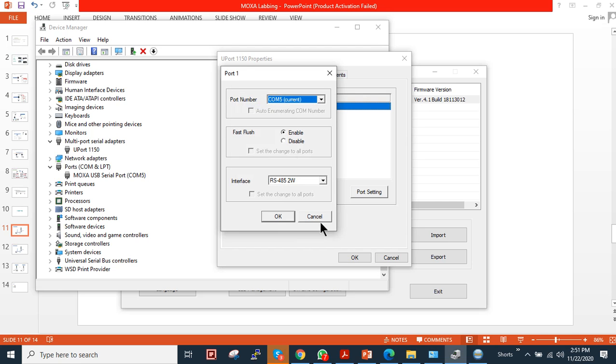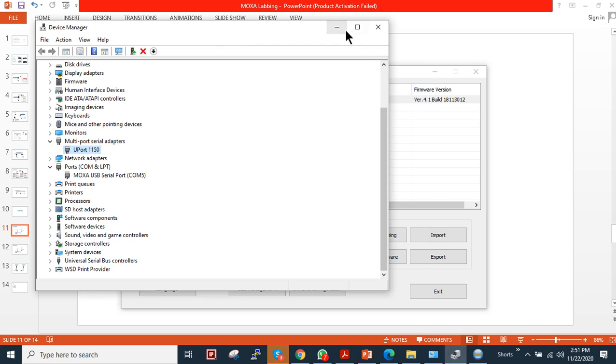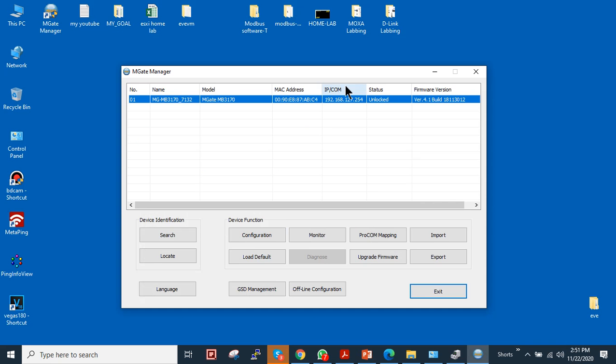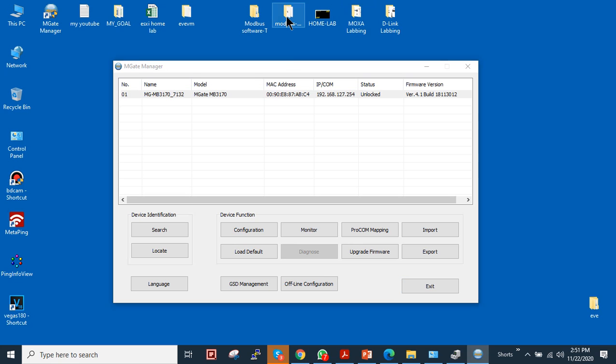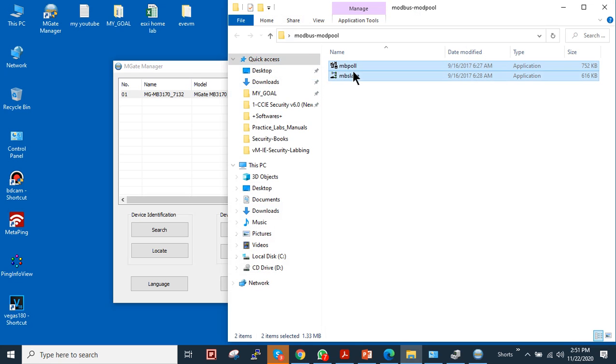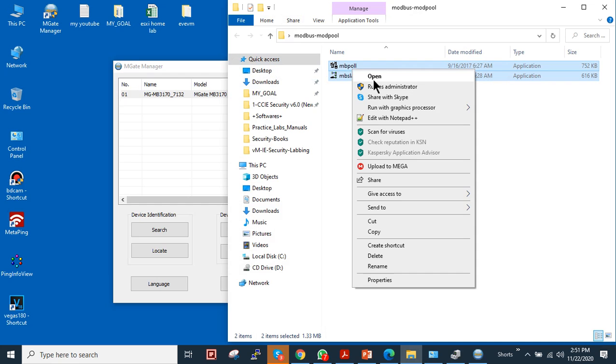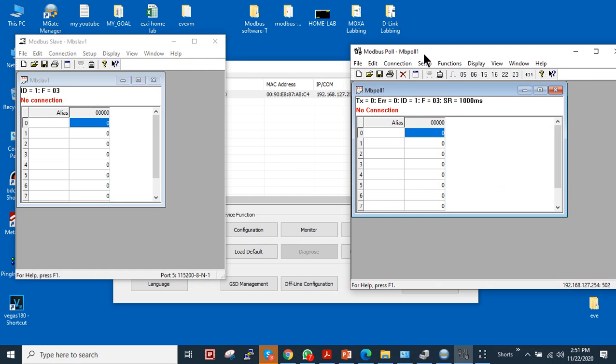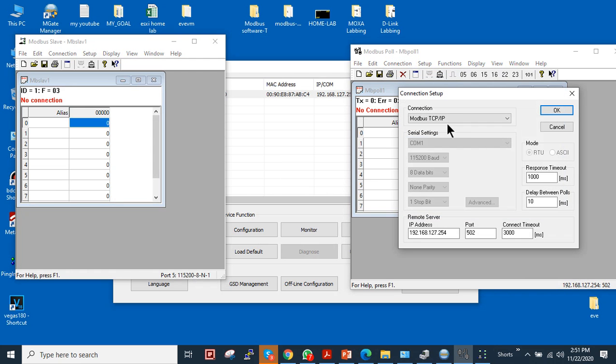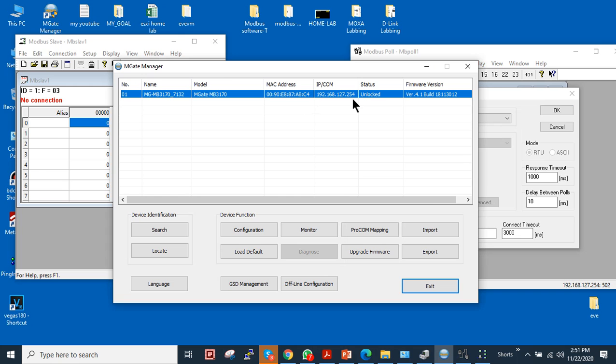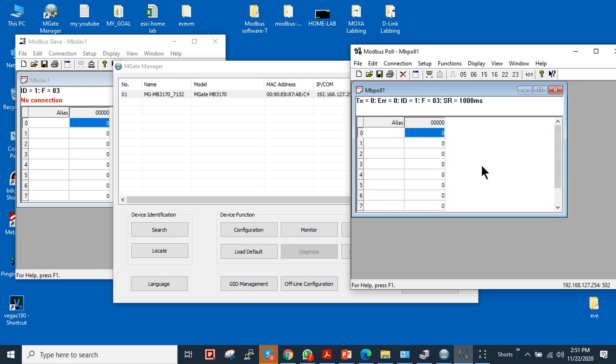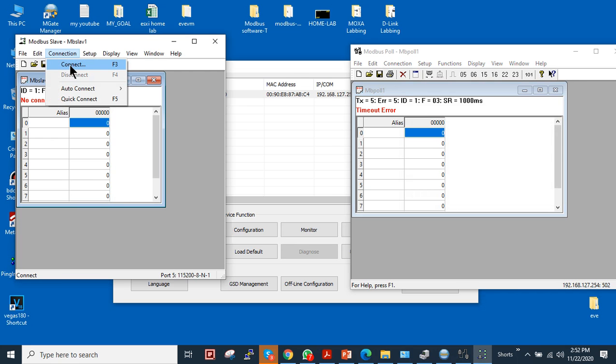Besides this, I'm going to use this Modbus simulator software. I will open the software simulator and I will connect first the TCP/IP interface, Modbus TCP/IP. The device IP is 192.168.127.254. In my case, you can choose according to the requirement, whatever IP is configured for the Modbus device. In my case it's .254, so I am going to use .254 here and port 502 as I showed you in configuration. I will just click on connect.